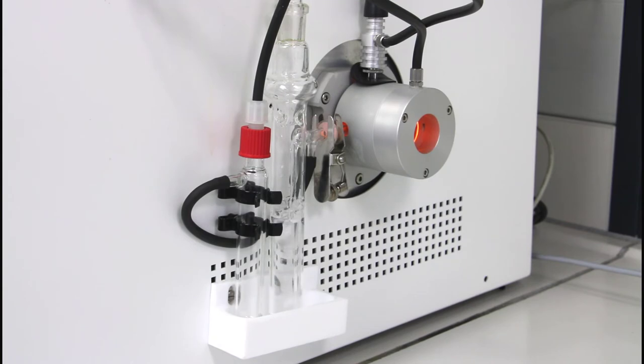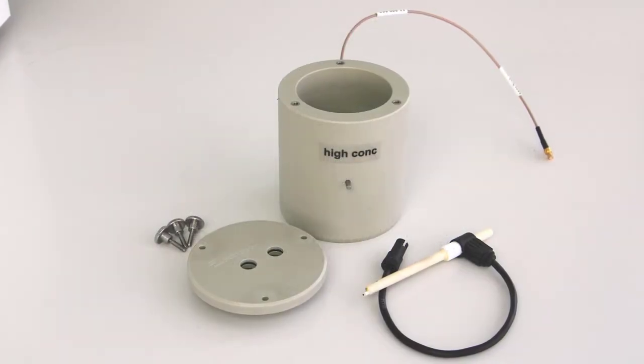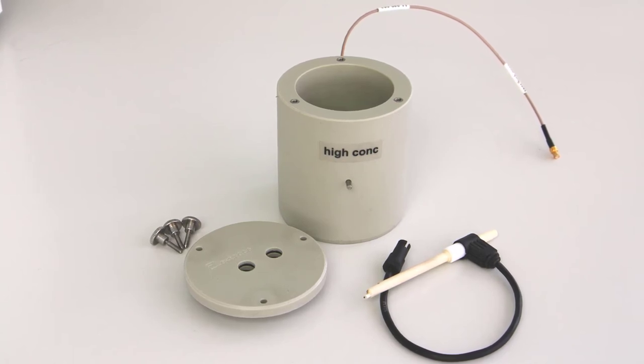Following the combustion and drying in the sulfuric acid, the gases will be transported into our microcoulometric titration cell. Light protected and cooled by an integrated Peltier element, there is no drift effect present.